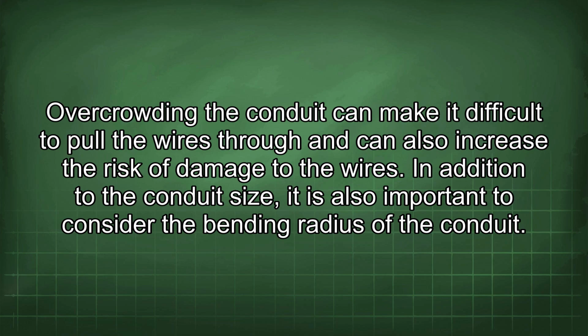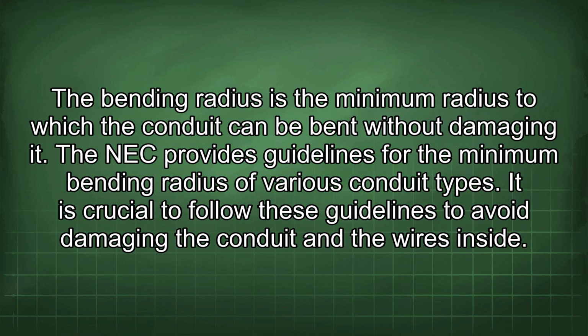In addition to the conduit size, it is also important to consider the bending radius of the conduit. The bending radius is the minimum radius to which the conduit can be bent without damaging it. The NEC provides guidelines for the minimum bending radius of various conduit types. It is crucial to follow these guidelines to avoid damaging the conduit and the wires inside.